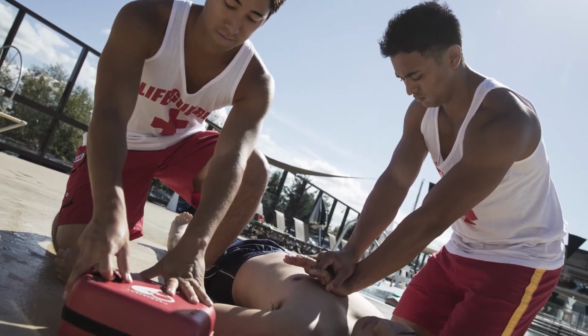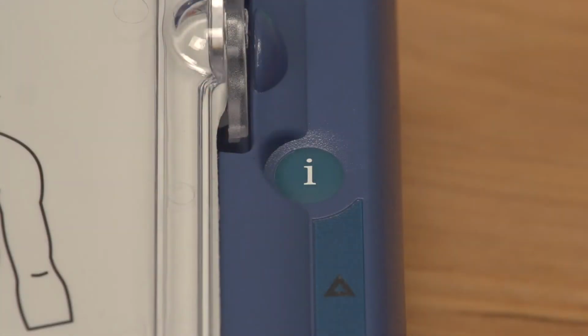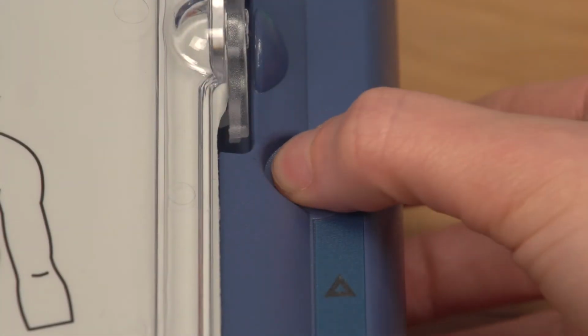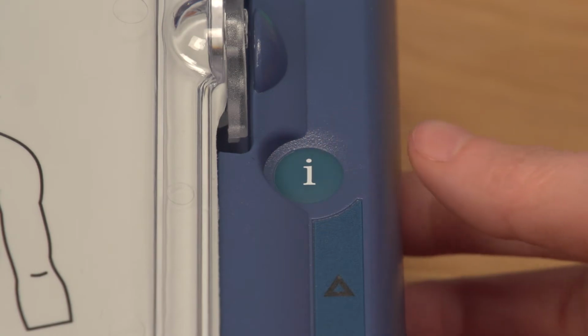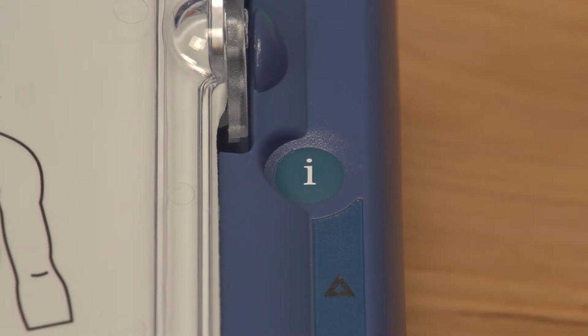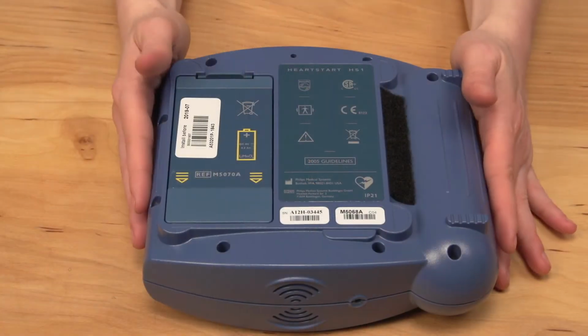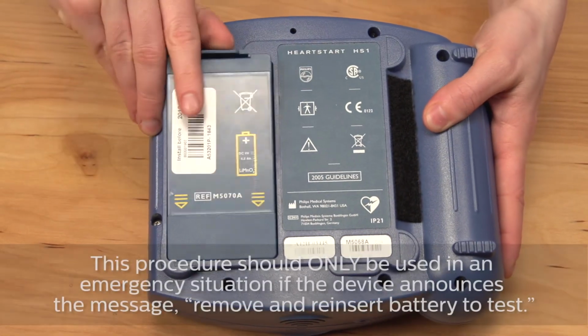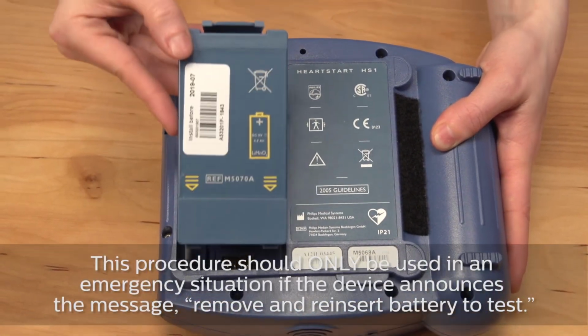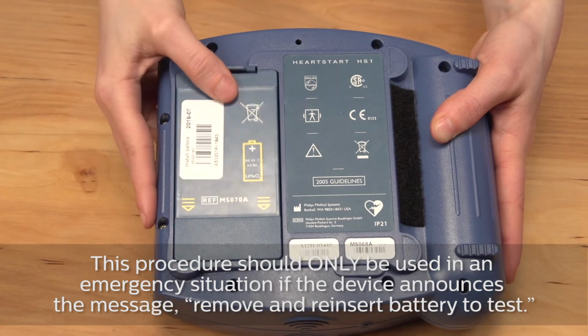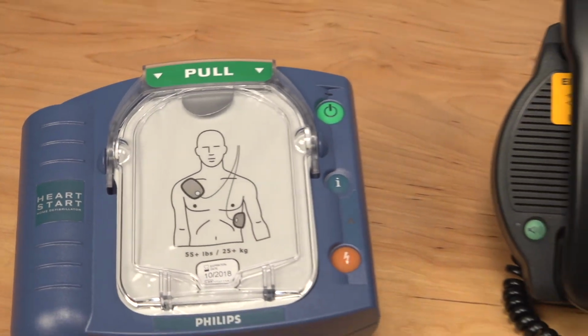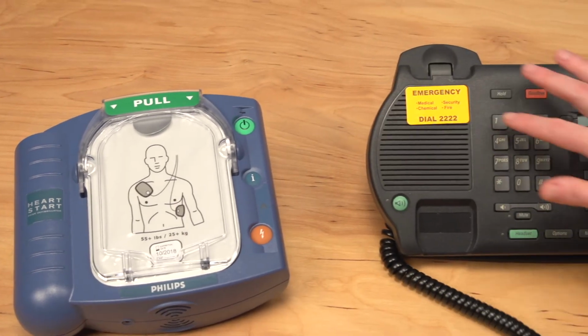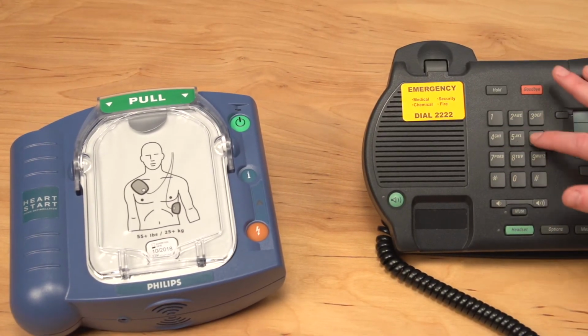In the unlikely event you hear triple chirps during an emergency rescue, press the flashing blue I button and follow the voice prompts. "Not ready for use. Remove and reinsert battery to test." Removing and reinserting the battery during a rescue can temporarily clear some errors and may enable the defibrillator to deliver therapy. Once the emergency is over, contact Philips or your Philips representative immediately for technical support.